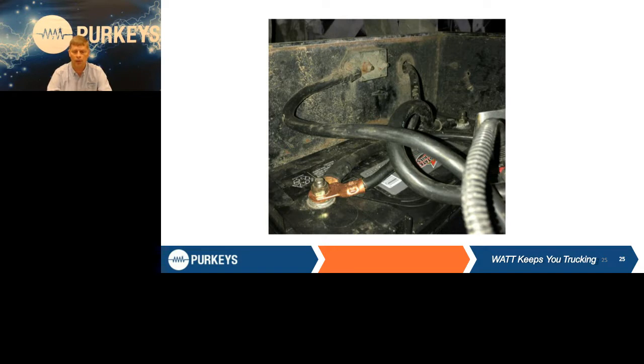Apparently that lug had broken off. Someone put a new lug on it and moved it directly to the battery. Well, yes, the gate works now, but guess what? That pump motor is not protected at all. You can very easily have a thermal event in this type of scenario.